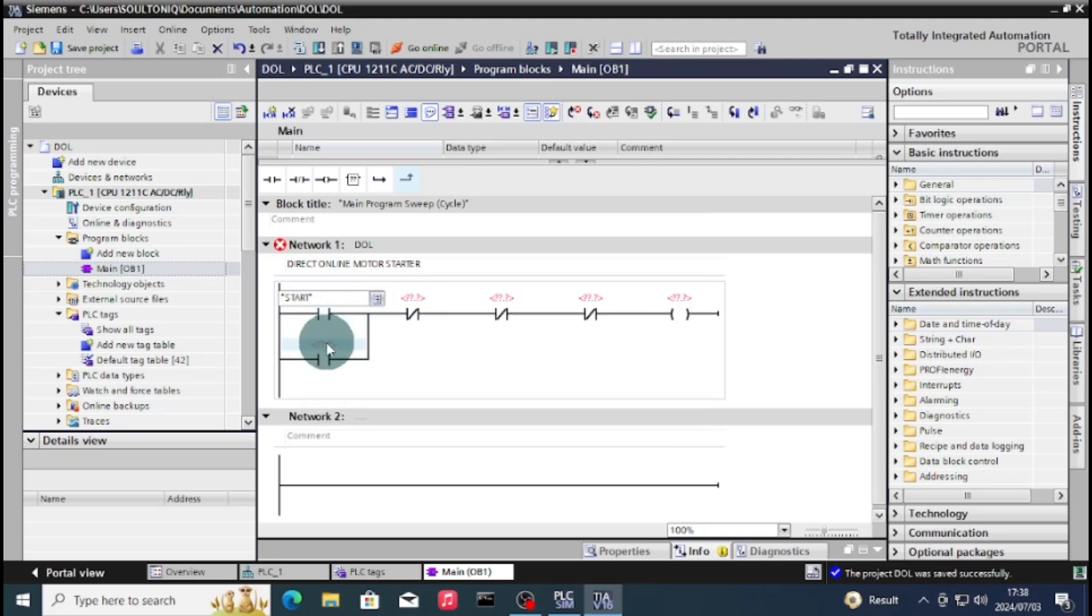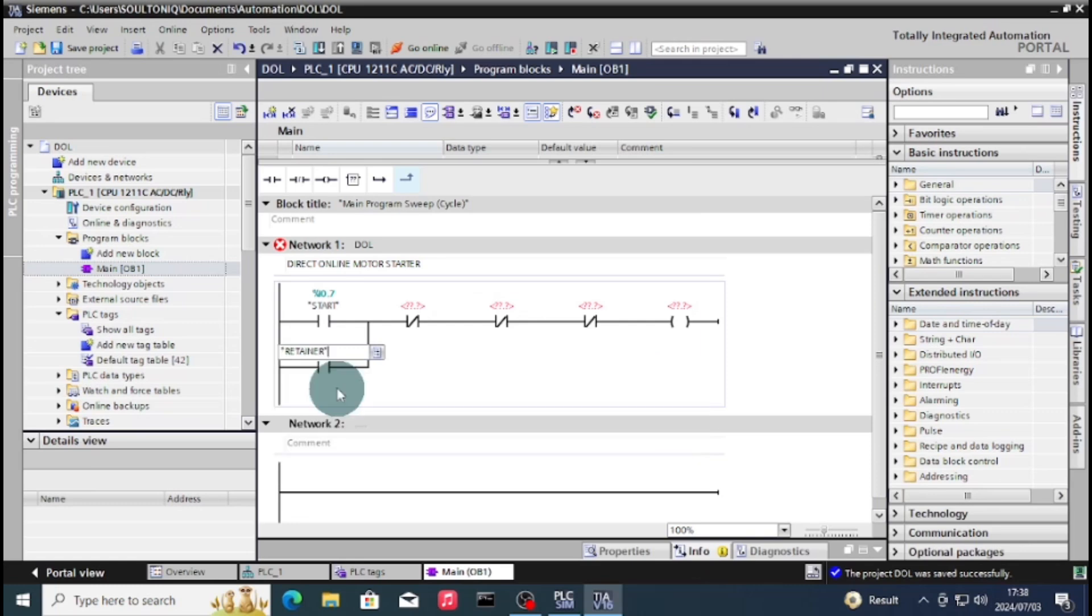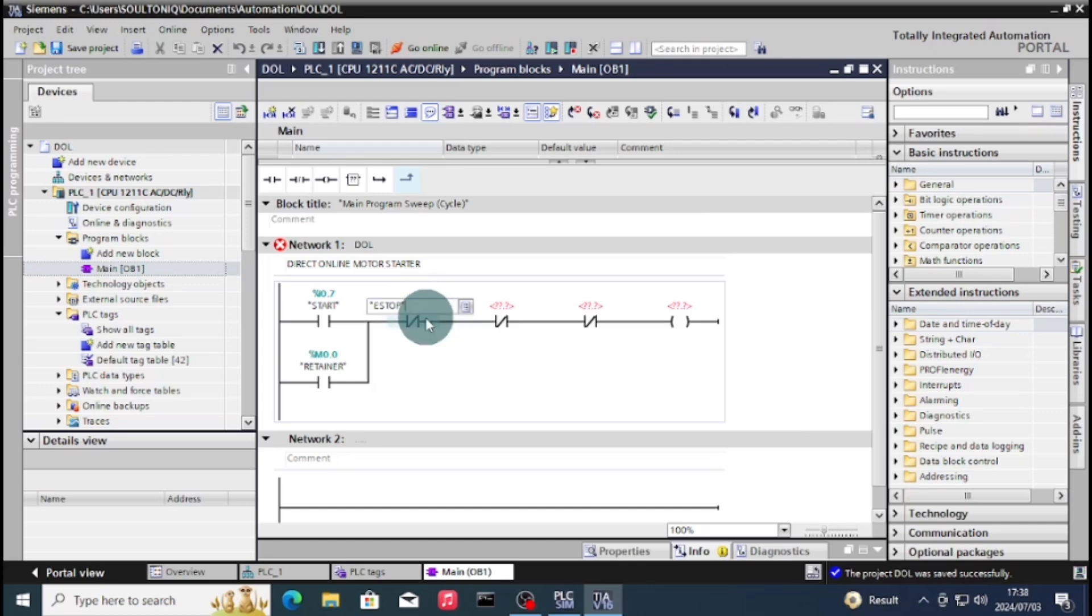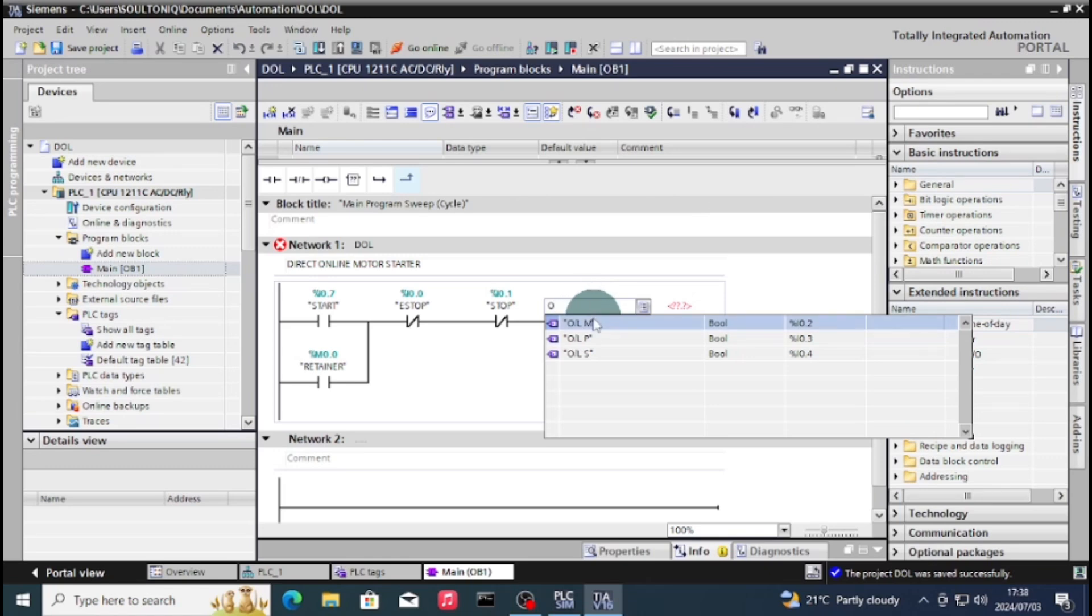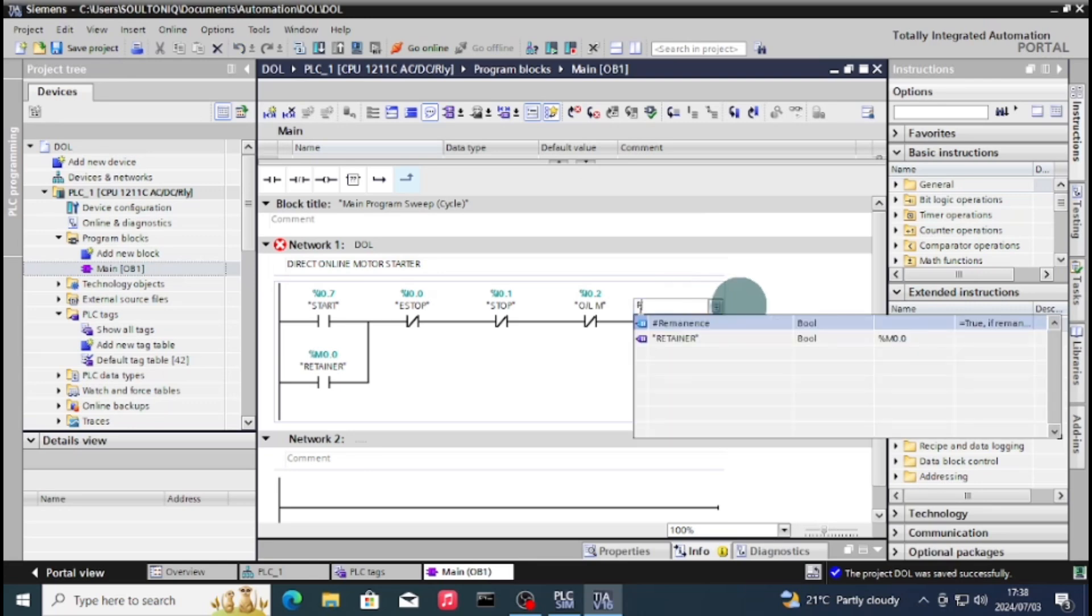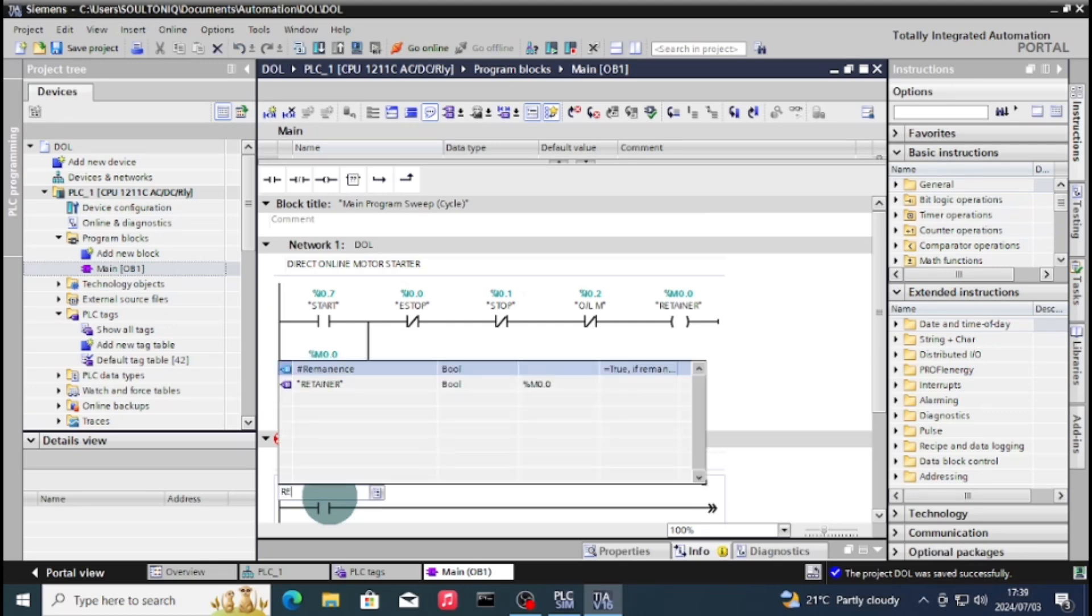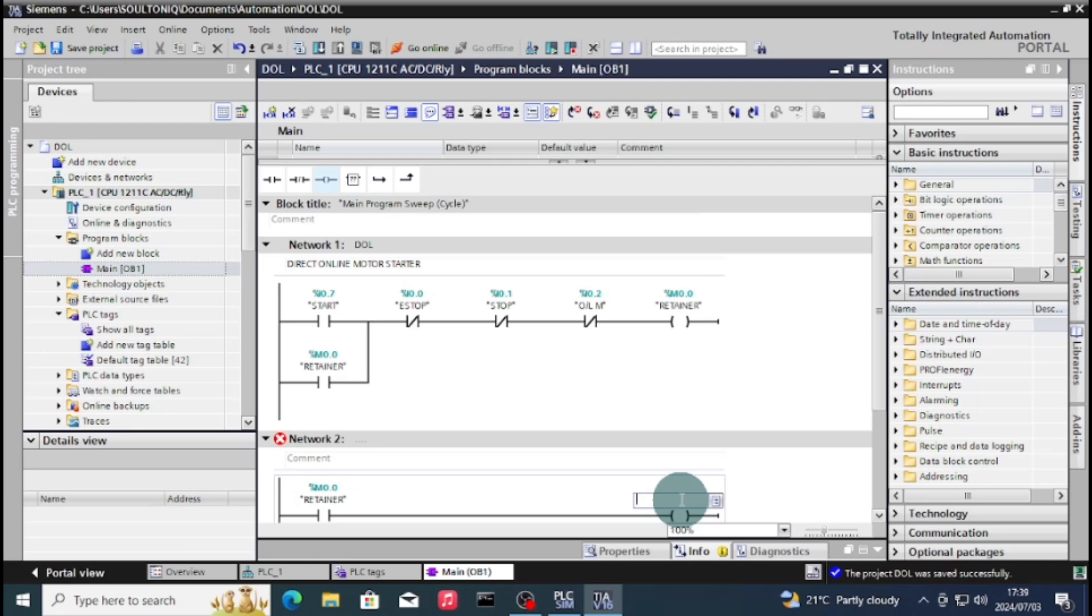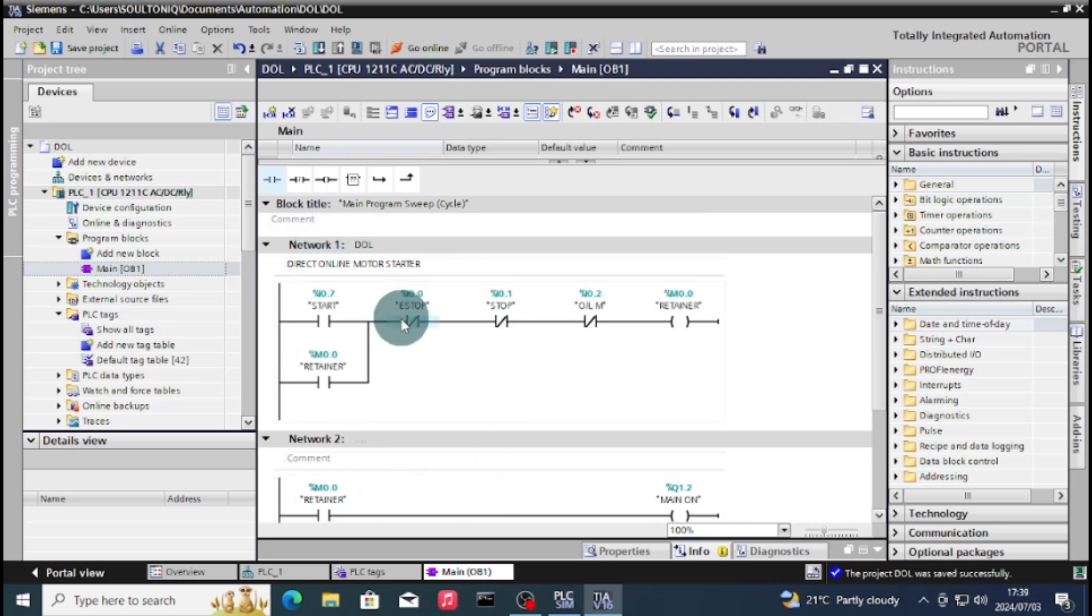So this is my start. I'll put a retainer here. I like to use a memory or the retainer bit - you can also check on the previous video on why I like to use them. We'll have a stop, and we'll have your overload. Our retainer is the main coil output. Because I remember this program also includes the star delta starter program, so this is our main contact that's going to switch on the motor.